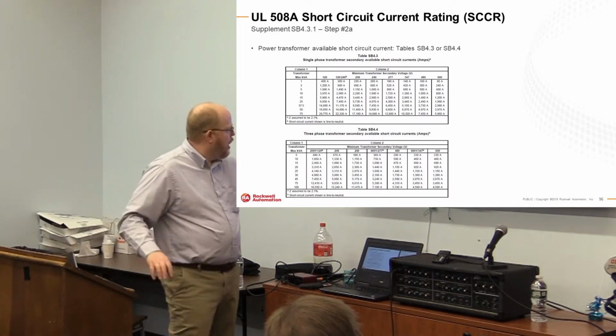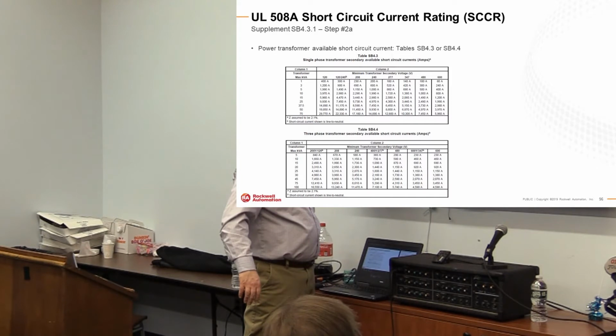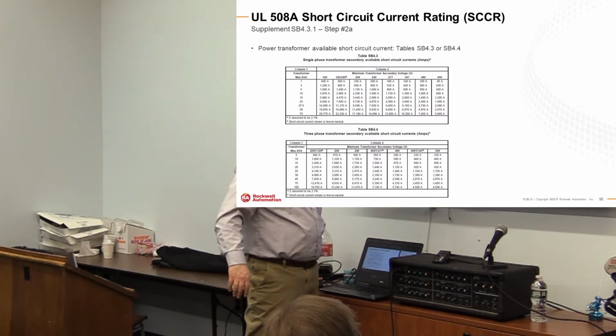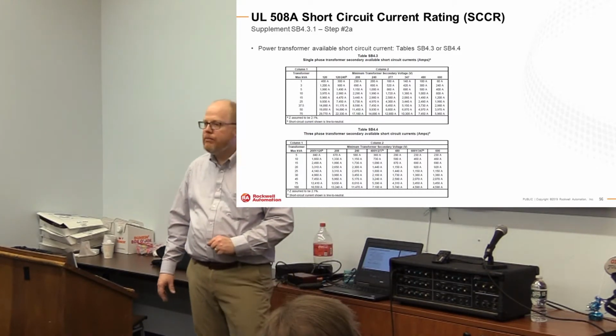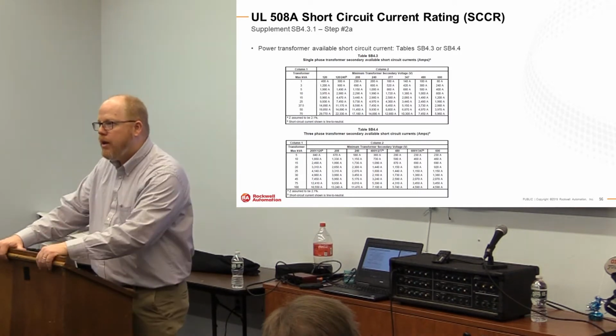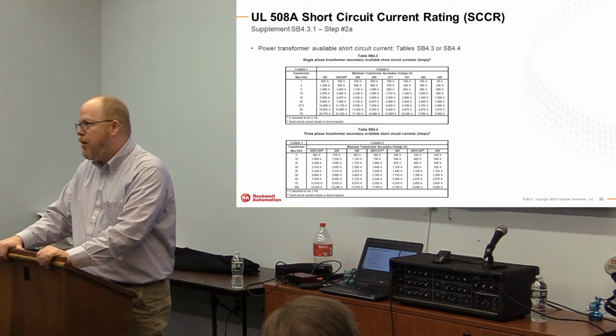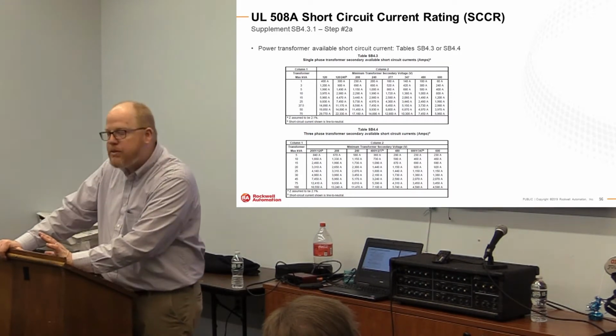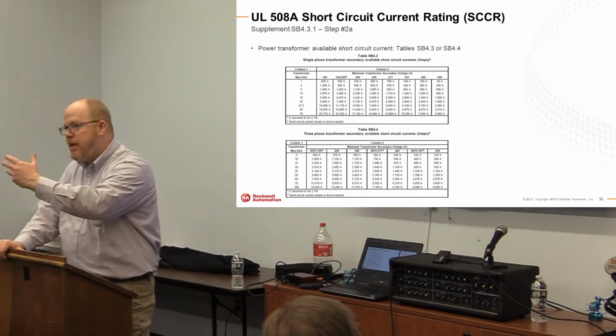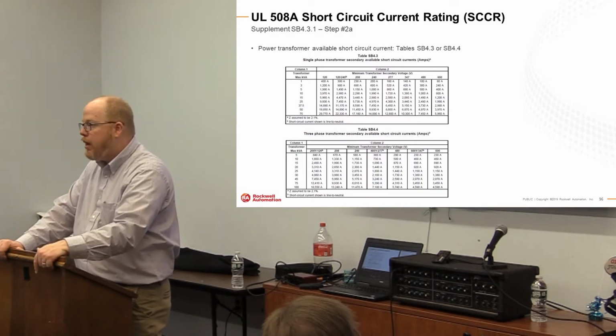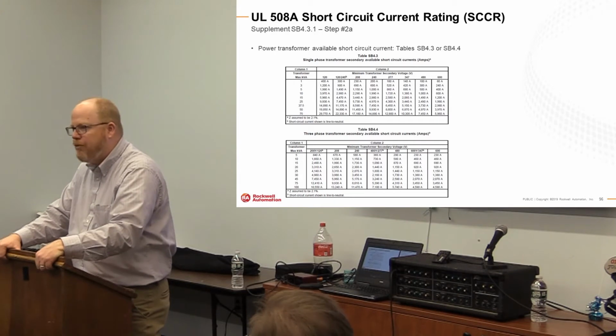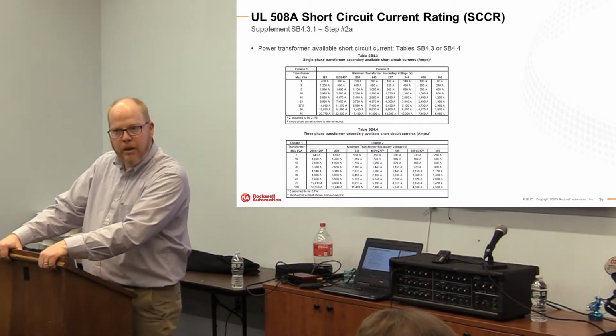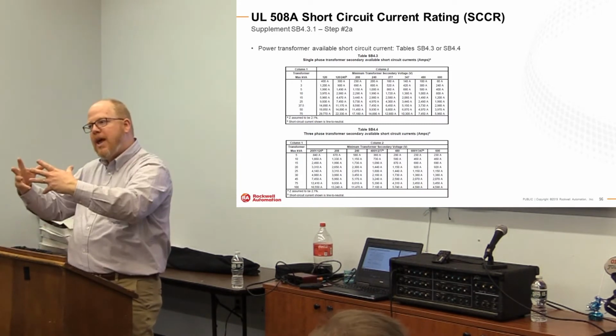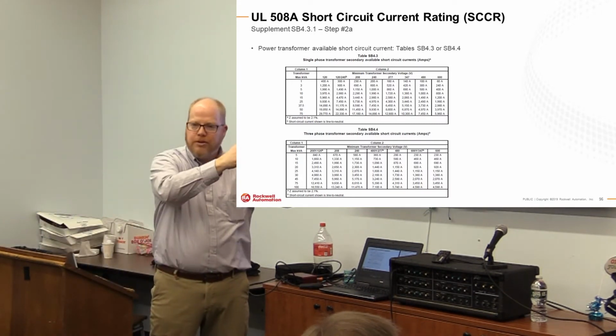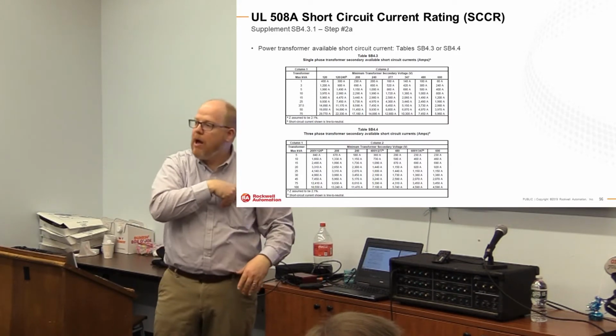So what you can see here, for example, we have a 480 volt Y transformer at 100 kVA is 7,180 available short. So that 100 kVA transformer, at 480 volts, can pump out roughly 7,000 amps of short circuit. Well, if I have a 10,000 amp device down below, that's okay. But if I only have a 5,000 amp available fault withstand, that is not good. So again, you would square what components I have in my branches and feeders with the source that it's giving here, in this case, 7,000 amps.